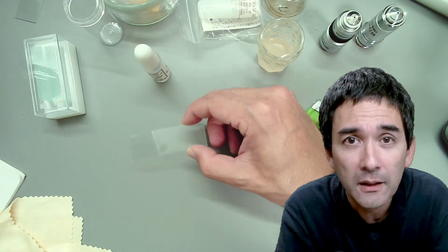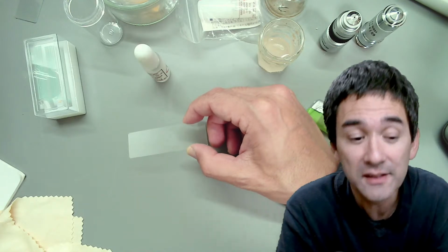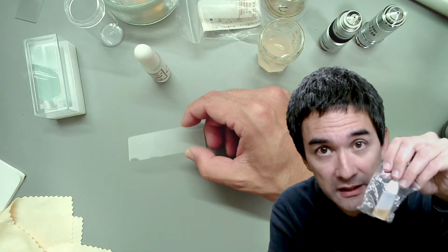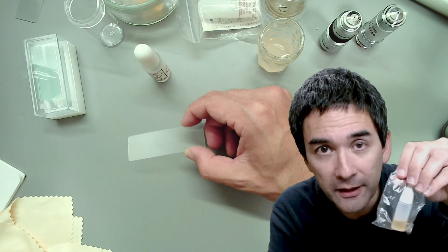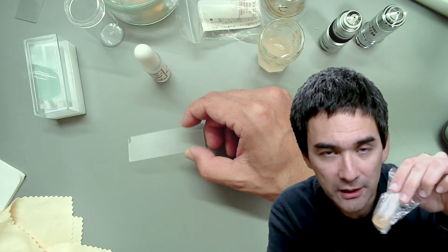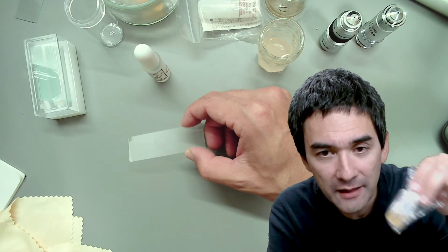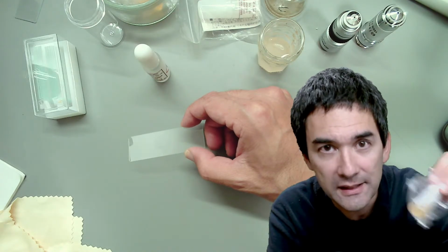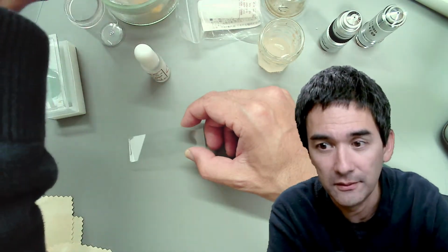Number one, it's going to collect dust otherwise. And number two, remember those oils that I showed you before, the yellow ones, they solidify over time. You really want to make sure that if you use those natural immersion oils, you have them removed. Otherwise, they are going to turn hard on your lens, and you don't want that.